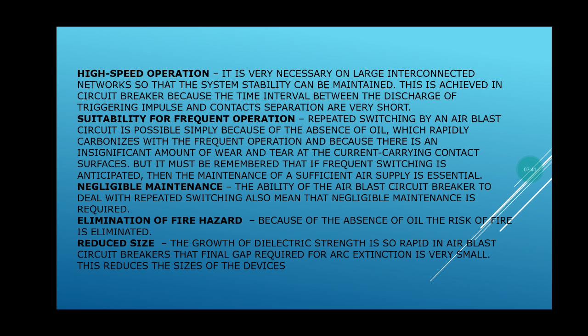Reduced size. The growth of dielectric strength is very rapid in air blast circuit breakers. The final gap required for arc extinction is very small because the dielectric strength grows rapidly, so the size required is very small. We can install the internal objects very closely, which directly reduces the size of the device.